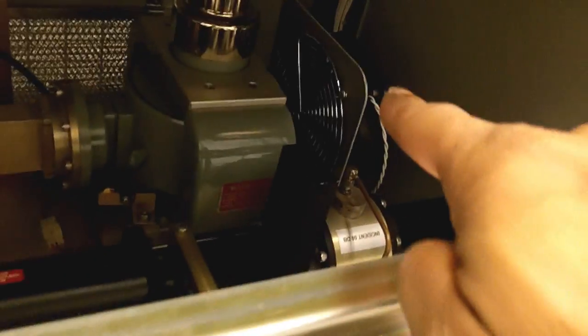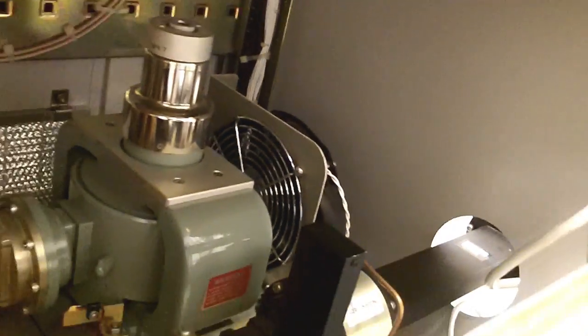And right back here in the back, I'm not going to put my hands in here because the voltage is very high. But that cooling fan right here is barely spinning, as you can see. Barely spinning, that needs to be replaced. And there's another fan right up here in the rack. You see that spinning? That fan is not spinning. That's actually gone too. And a few other devices back here that have fans, which probably need to be replaced.